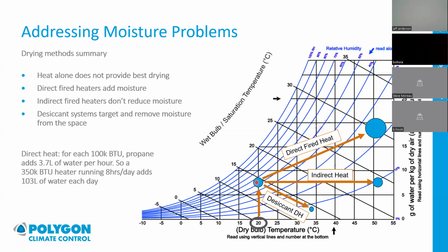And you can see this blue ball going from this condition to this condition using direct fired heat has gotten a lot bigger. So I'm just doing that to show you that when you're using direct fired heat, you're adding water. A quick and dirty calculation would be if you had propane fired heaters on a site, for each 100,000 BTU that they're rated at, you get about 3.7 liters of water per hour that's being directly pushed into the air that's going into your space.